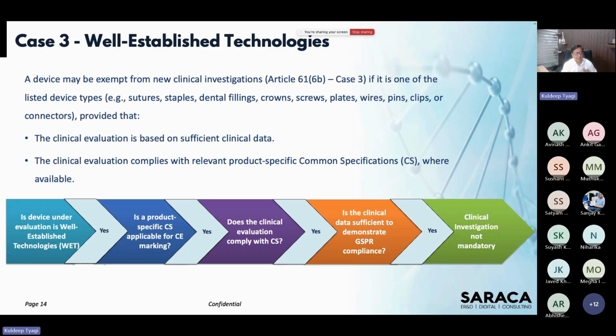But you have a sequence here. Is the device under evaluation a well-established technology? If yes, is a product-specific CS applicable for CE marking, which we have to see in the regulation? If the answer is yes, then does the clinical evaluation comply with the common specification, right? So you will have to relate what is the requirement of the common specifications. Do you have that in your design input, and is your design output ensuring that it meets the requirement of design input? Have you really considered risk associated with all the common specifications as per 14971, the latest standard? If you have done that, the next step is: is the clinical data sufficient to demonstrate GSPR compliance? And if the answer is yes to that, you don't have to go for clinical investigation.